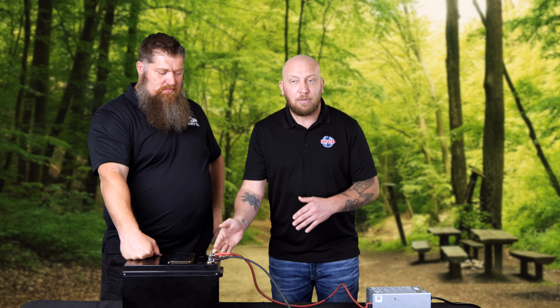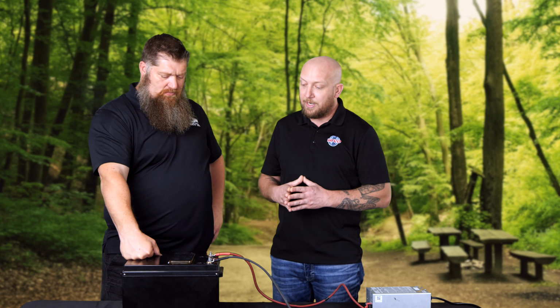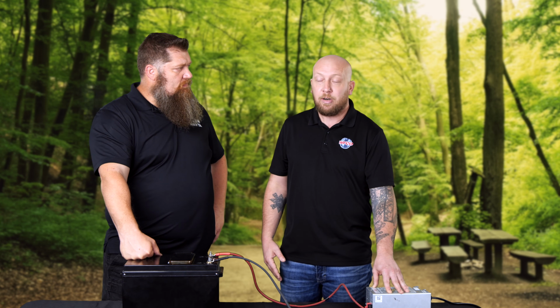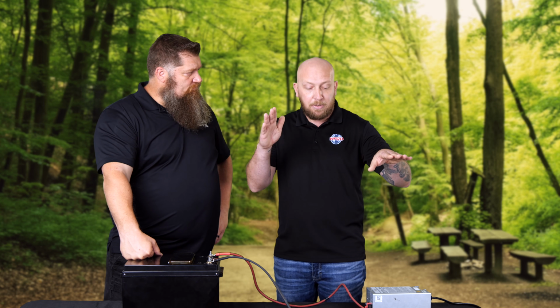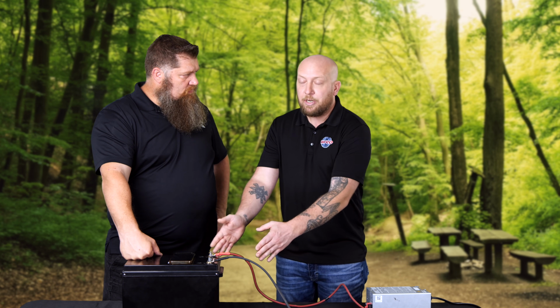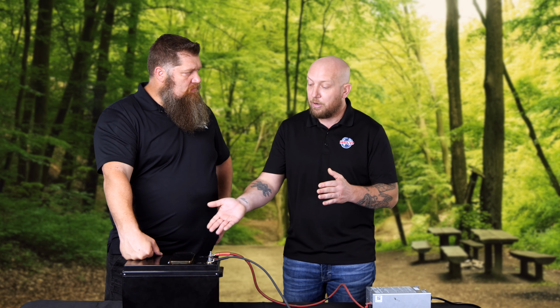But if that's not possible, what I recommend for customers dealing with a large voltage drop - meaning the voltage from your converter isn't getting to your battery, resulting in low amperage charging - is installing a deck mount converter closer to your battery. Even with a power center, I'd disable the converter inside it, use the power center just to hold your breakers and fuses, and install a deck mount converter closer to your battery to give you the charge you're looking for, because the converter cannot make up for that voltage drop. It's up to you to either boost your wires, shorten the distance, or relocate a converter closer to get that voltage to your battery.